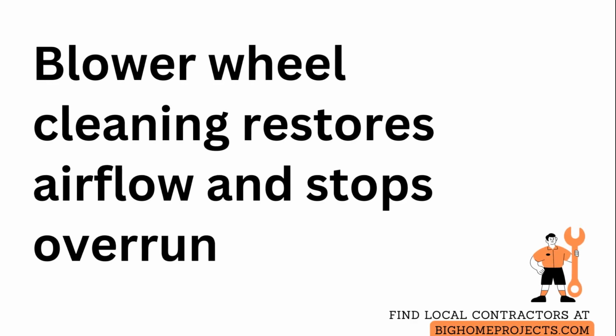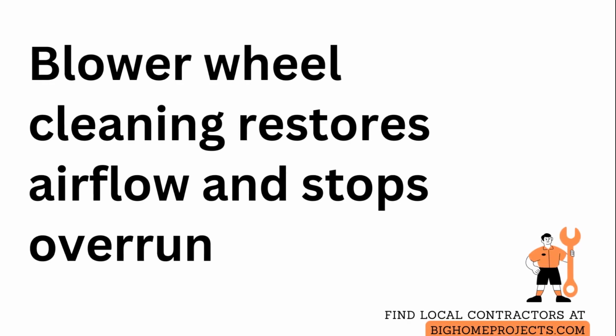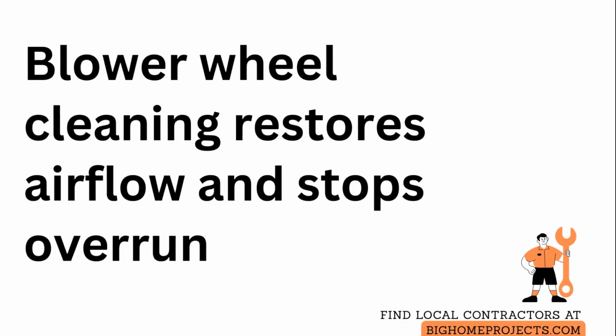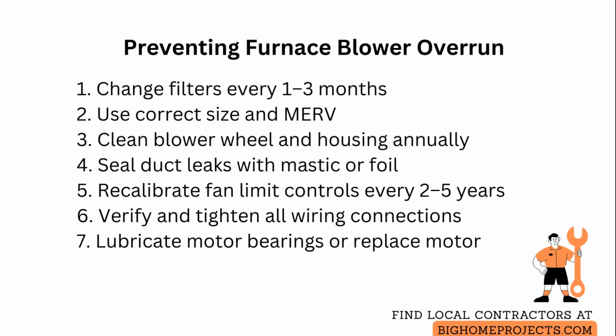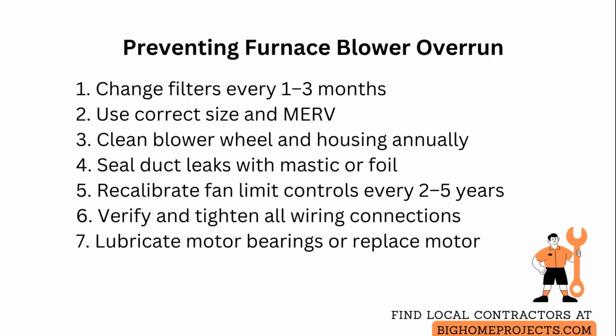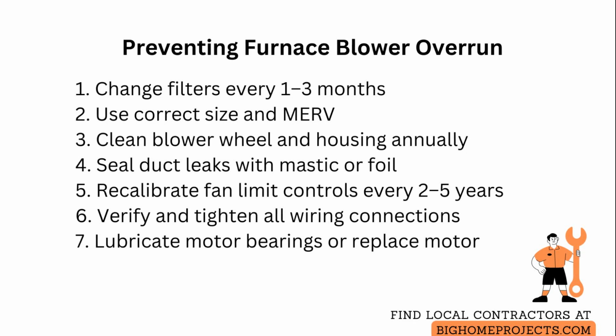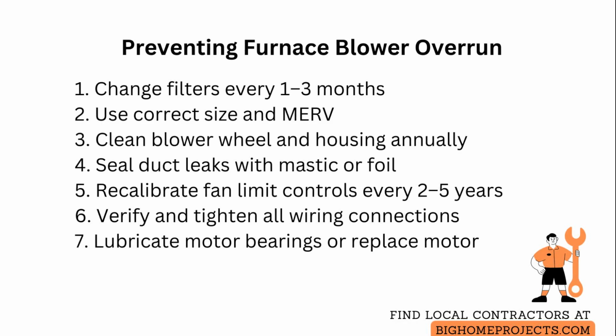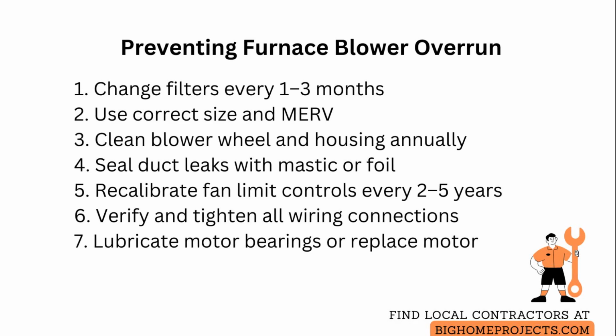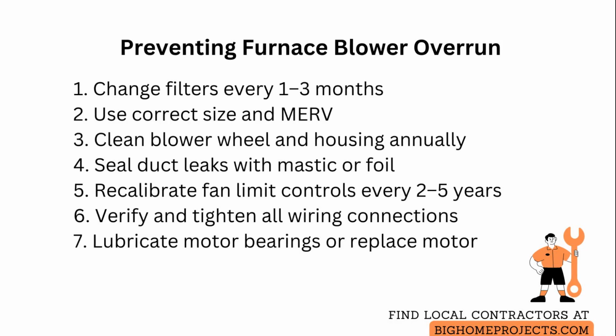Preventive maintenance on furnace blower motors prevents most overrun problems before they start. Change filters regularly using the correct size and minimum efficiency reporting value for your system, and replace them every 1 to 3 months, depending on load. Clean the blower wheel and housing annually by turning off power at the service switch, removing the access panel, and gently brushing or vacuuming accumulated dust and lint to restore balance and airflow.